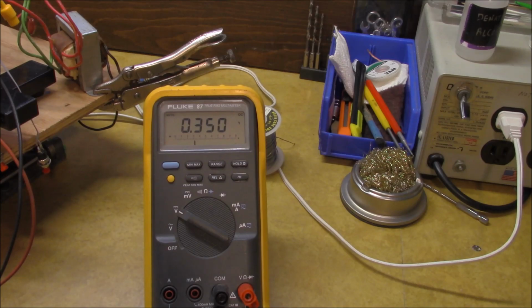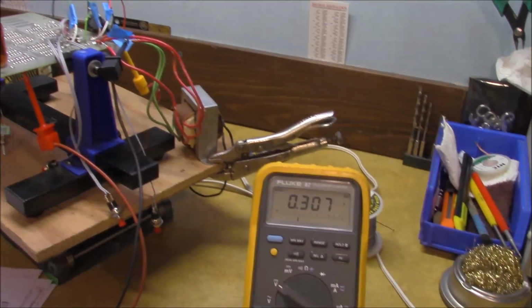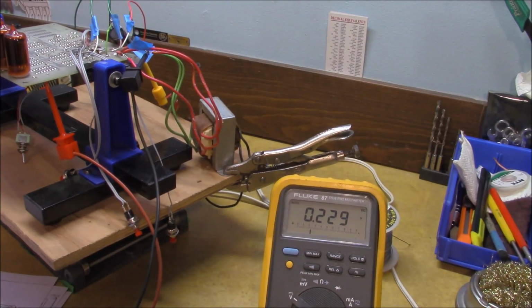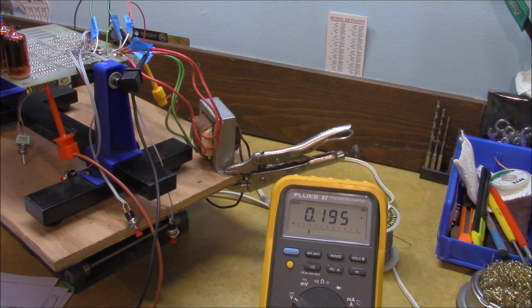Without the high voltage wires on the board from the transformer, the logic supply appears good. I have traced the high voltage section on this board, and I am not seeing any dead shorts or anything that's pulling it down.